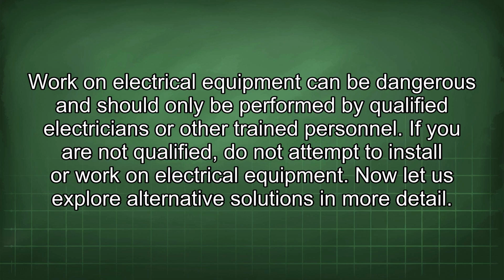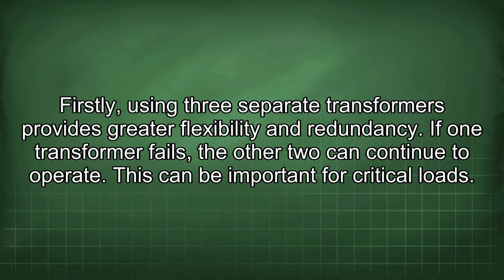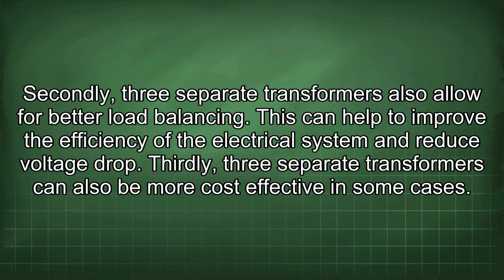Now let us explore alternative solutions in more detail. Firstly, using 3 separate transformers provides greater flexibility and redundancy. If one transformer fails, the other 2 can continue to operate. This can be important for critical loads. Secondly, 3 separate transformers also allow for better load balancing. This can help to improve the efficiency of the electrical system and reduce voltage drop.